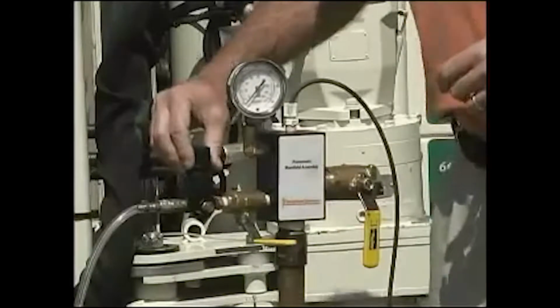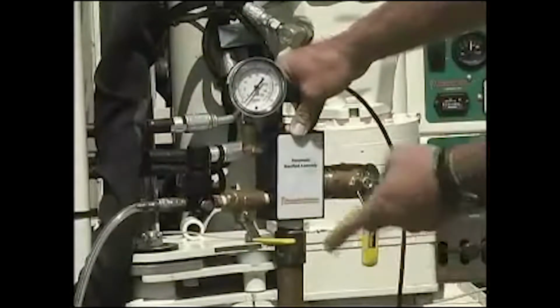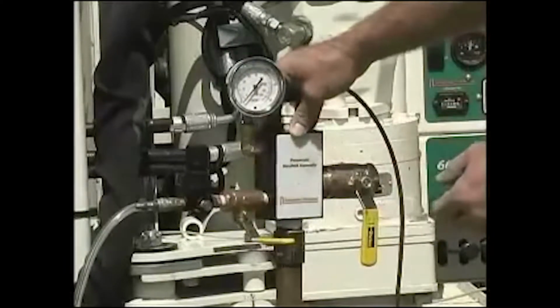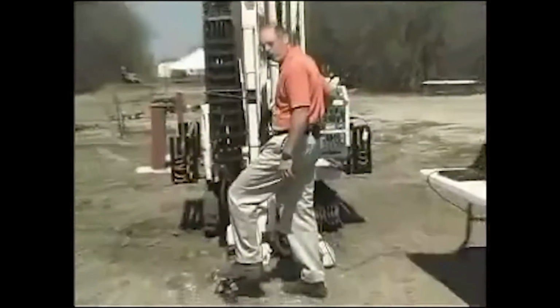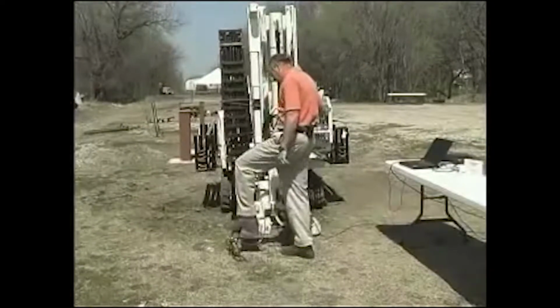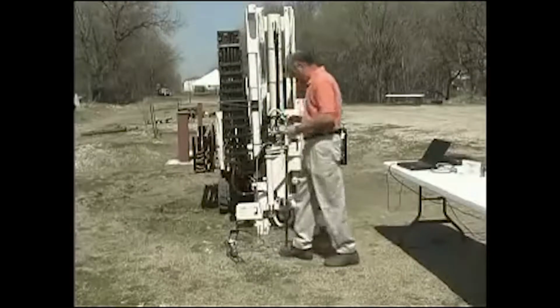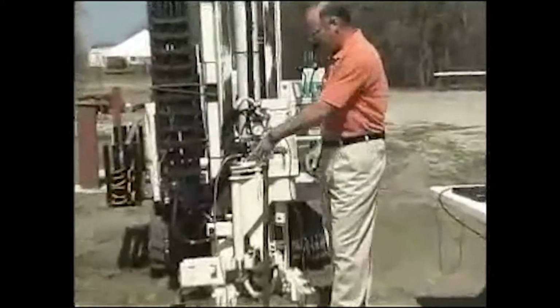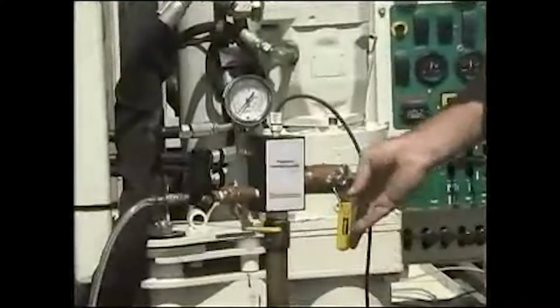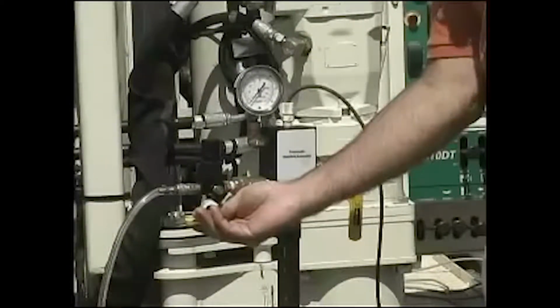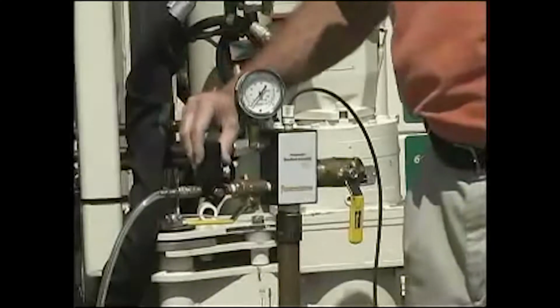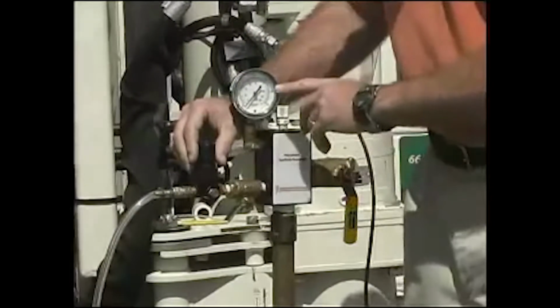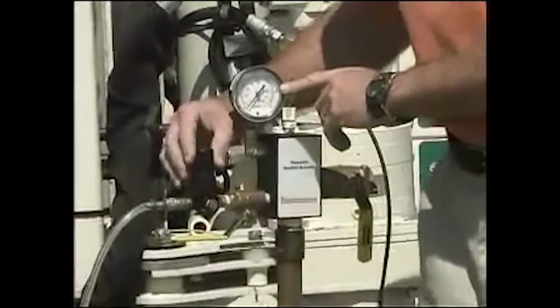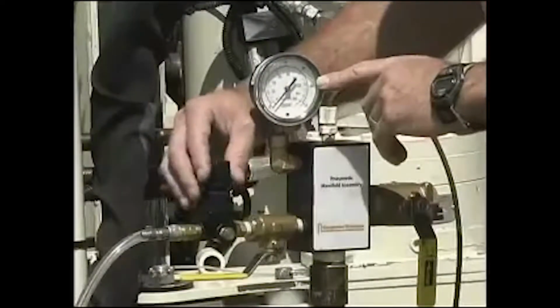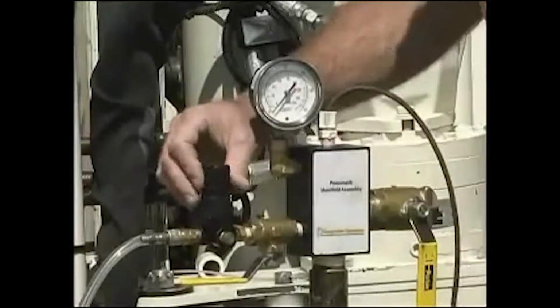And so next what I'm going to do is pump a few psi of air into the tubing with our foot pump. This is really about the hardest part of this job. Okay, so I've got about 30 or so psi of air in the tube system. This is closed. Now I'm going to open the inlet valve here. And now I'll start opening the pressure regulator, and I'll have to turn it around a few times, and we should start seeing air come into the system. The gauge will go up.